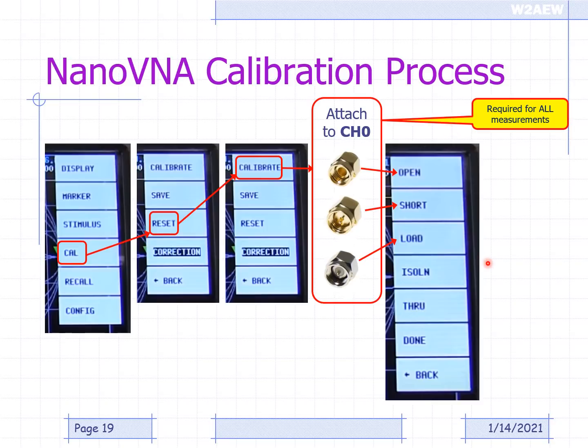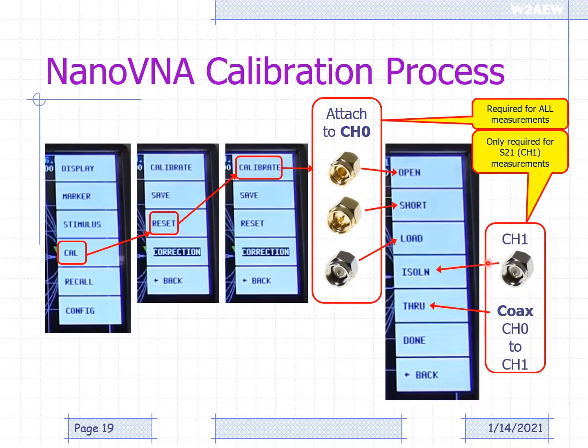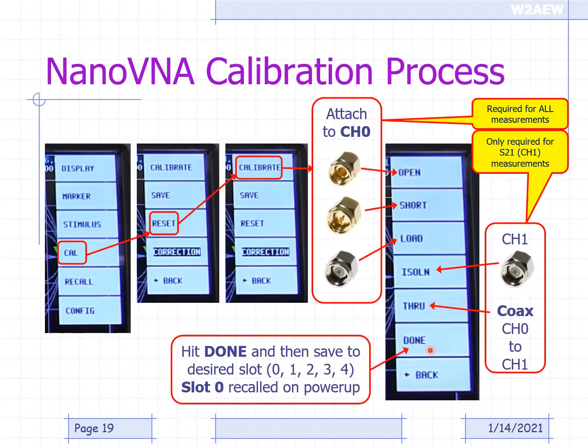If you're going to be doing some through measurements, then you also want to do the isolation and through calibrations by attaching the load to channel 1 and then connecting channel 0 to channel 1, do a through, hit done, and then you can select what slot you want to save in. Now, if there's something that you're going to do most commonly, you can save that result to slot 0, and that's always recalled on power up. So the thing could power up right the way that you want it.